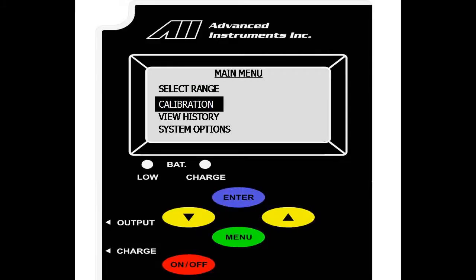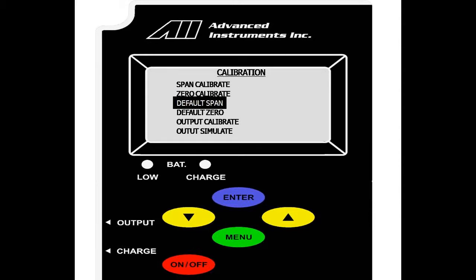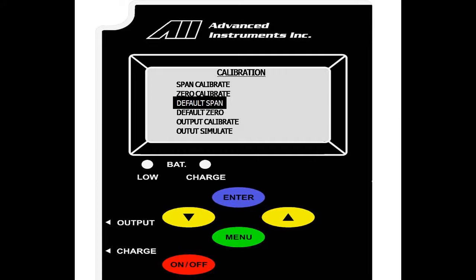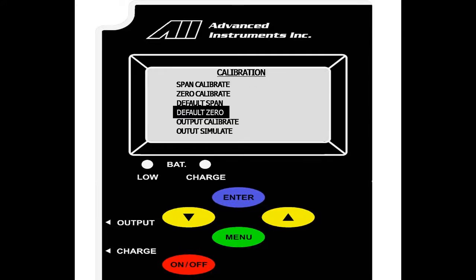As you can see, the sensor has responded and we will now select menu to go into the main menu and scroll down to calibration. We select enter and are taken to the main calibration screen. Prior to doing a span calibration, we will perform a default span and a default zero. This clears off any prior calibrations done to the sensor and resets it to default settings. We select enter on default span and are prompted with factory default set. We repeat this with default zero and again prompted with factory default set. This shows us that the sensor has a raw output now and any calibrations have been removed.